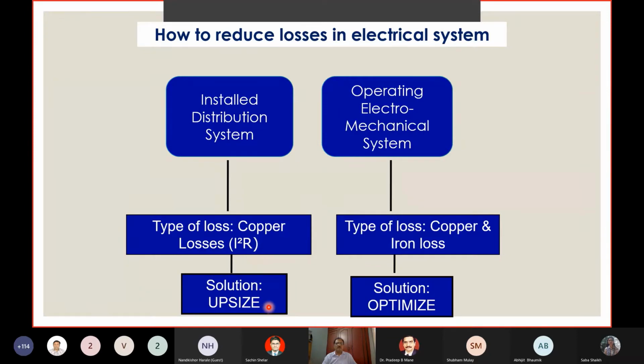The solution is in one simple word: upsize. So when you have a switchgear or a cable or a bus bar, if you increase the cross section, or increase the number of bus bars and number of cables, then you will be able to reduce the resistance. This is what I mean by upsize. So for the installed distribution system, upsize is one opportunity available to reduce the I²R losses, because we will be reducing the resistance. A few slides are there where I have explained this in detail based on our studies.